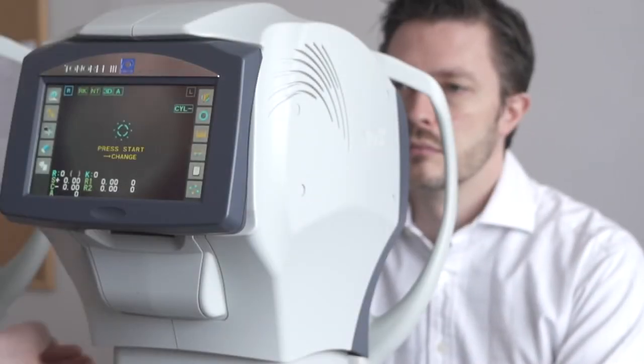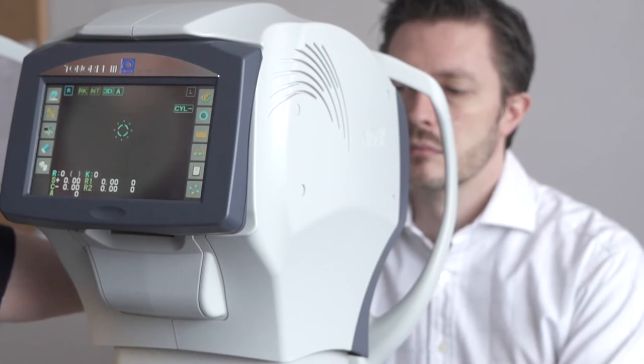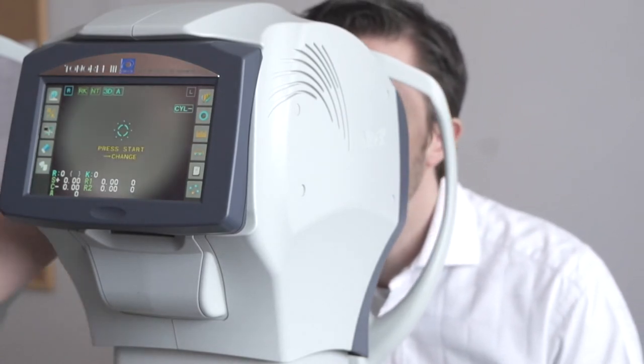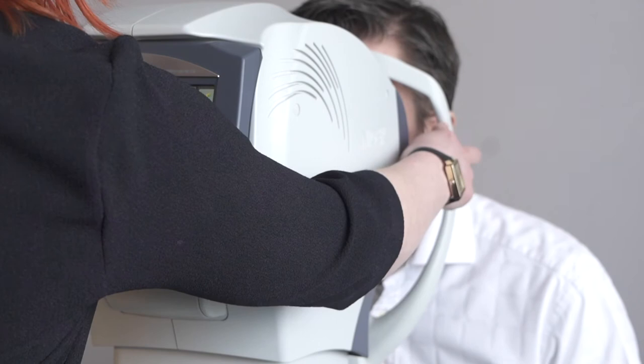The patient should be aligned by asking them to place their chin on the chin rest and forehead against the bar. We're looking to align the outside of the patient's eye with the canthus markers on the sides of the device.